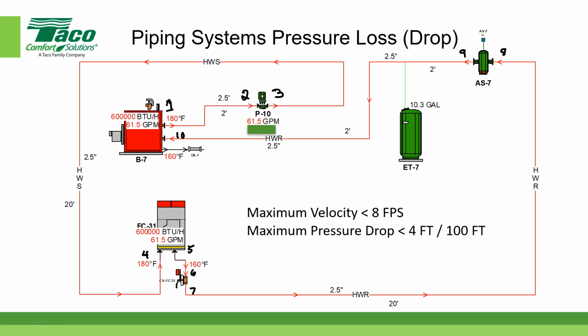As Rich is moving from screen to screen, I do want to re-emphasize that this is for HVAC hydronic calculations. This is not for domestic or anything like that, right, Rich? That's a different ballgame. You could use the same methodology for domestic water, but you typically have different design criteria. Instead of allowing 8 feet per second, domestic water is usually much less of allowable velocity. And the pressure drop per 100 feet for domestic water might be different. So the design criteria for the HVAC system that we chose is pretty common. The methodology for doing the pressure drop calculation for domestic water is the same, but you usually have different criteria that you're trying to stay within. But for today's discussion, it's only HVAC.